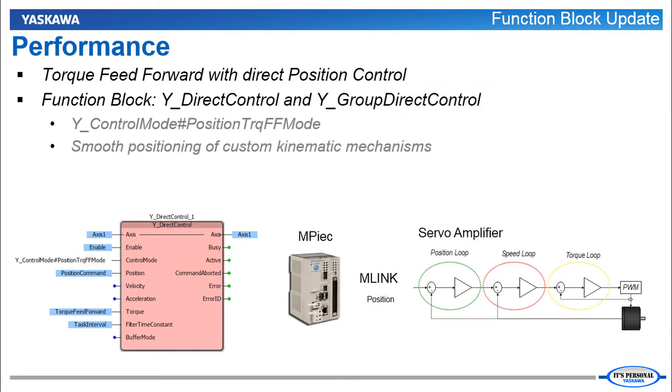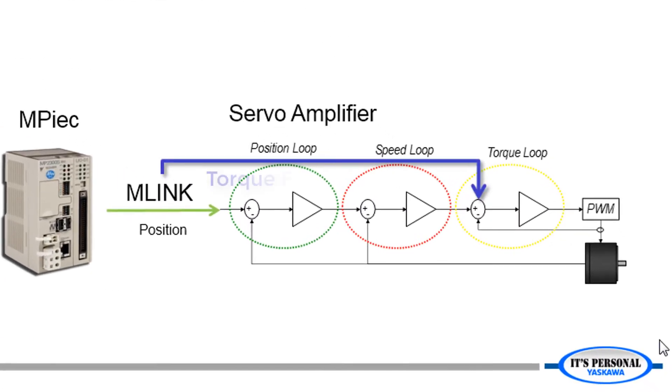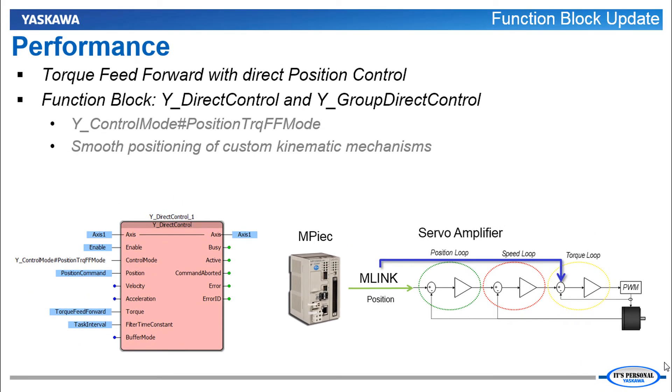Torque Feed Forward with Direct Position Control is helpful in positioning custom kinematic mechanisms. This allows the controller to command an estimated torque required for smooth motion of the mechanism. Leaving the position and speed loops to react to any remaining error more efficiently. This type of advanced control is especially helpful for these non-linear mechanisms.